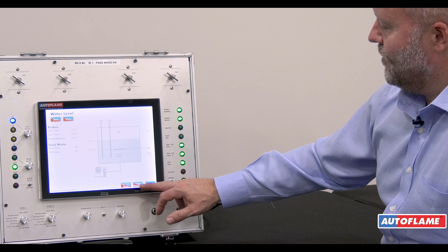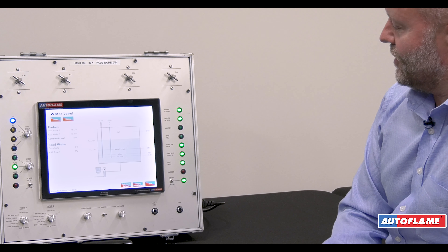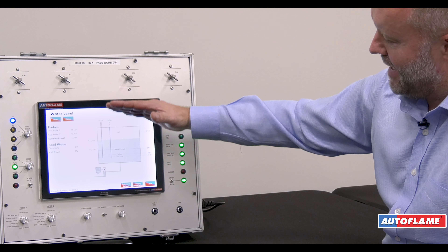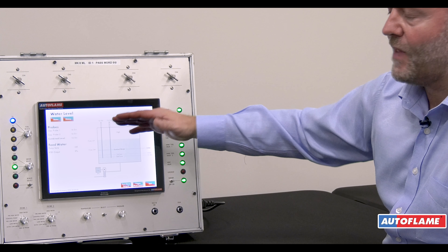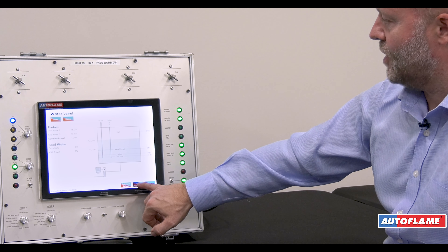We have test outputs and trigger a shunt, which is time related. When we trigger the shunt switch it means we're going to shut off the feed water and test all the levels on the probes without turning the burner off. This is our trigger shunt switch operation.